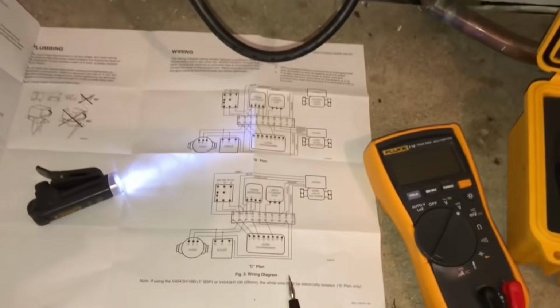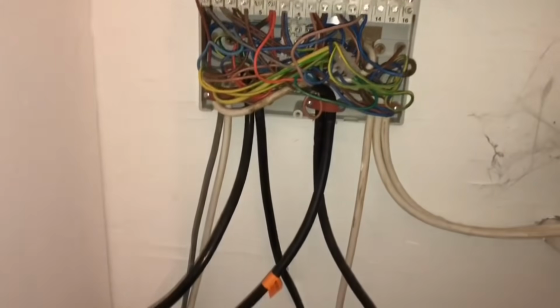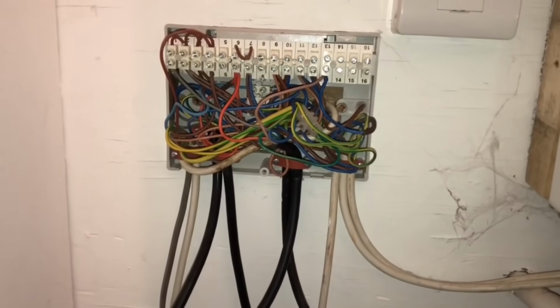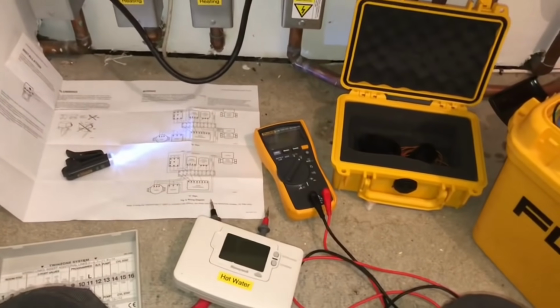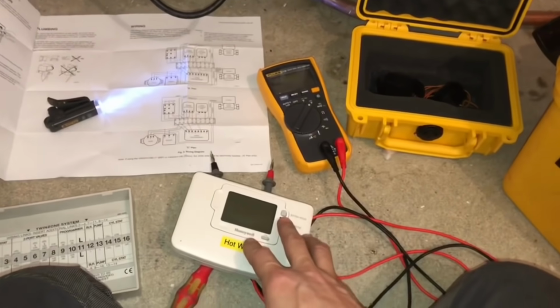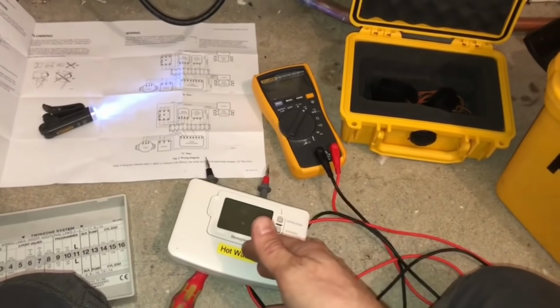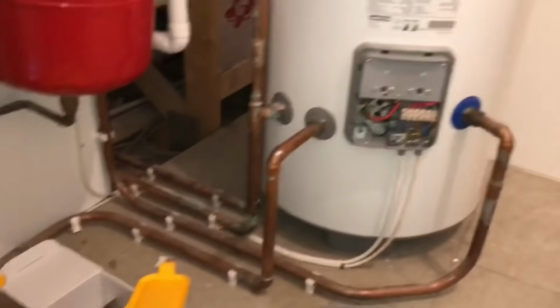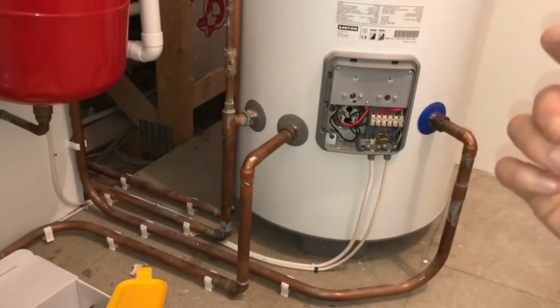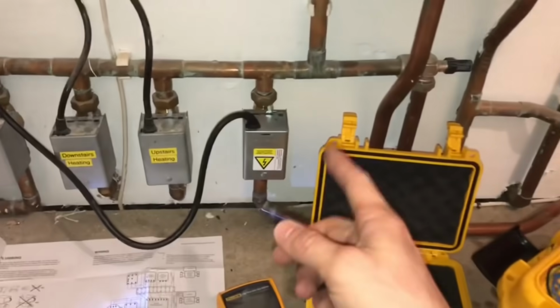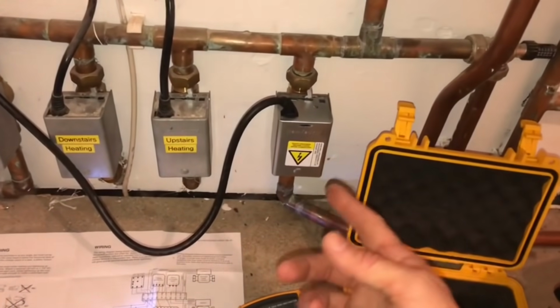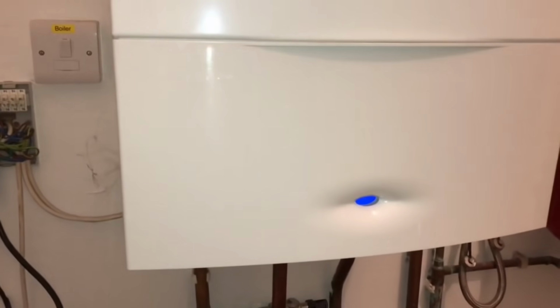Now you could look at a wiring diagram, but a lot of the time you'll find your wiring centre looks like this, which is no good to anyone. It can be quite daunting. So I like to break it down into a series. Now we always start at the programmer. The way it works is you call for a demand, the programmer puts voltage onto your cylinder stat. If your cylinder stat's calling for heat, it puts voltage onto the zone valve. If the zone valve opens, it sends voltage to the boiler and your boiler fires up.